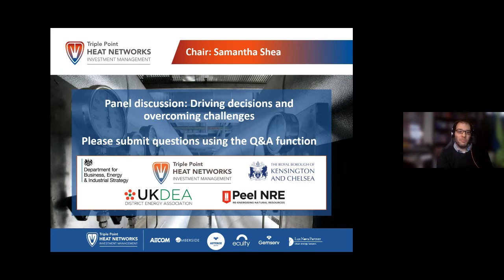So we looked at gas, which was close to the do-nothing option, but when it came to electrifying the heat, we looked at individual air source heat pump solutions, and direct electric heating, which is usually preferred on new developments from a building services point of view, especially for new builds. That's something that has to be treated per individual project, and try to develop it together with the project team and the client to see what fits better.